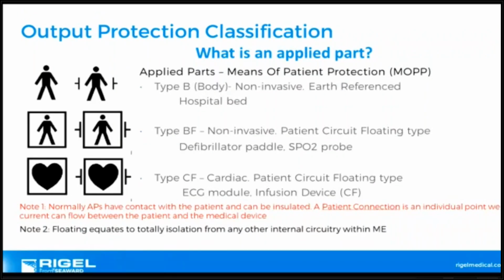The patient connection is the individual point where current flows between the patient and the medical device to do treatment. But the definition of applied part is that it's in physical contact. So there are medical devices out there that don't have applied parts, like for instance, some kind of light treatment doesn't have an applied part, this type of thing. But there are many medical devices that do have an applied part.